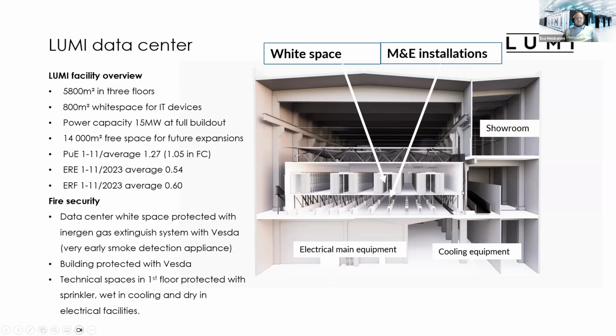So the data center itself is also 2 floors, so all the power connections and cooling pipes and network connections to the cabinets are coming from beneath, under the raised floor, which is 2.4 meters high, and all the electrical main equipment and all the cooling equipment is installed on the first floor. In this building, there is still over 14,000 square meters of free space for future expansions, so a couple more data centers of this size could fit.